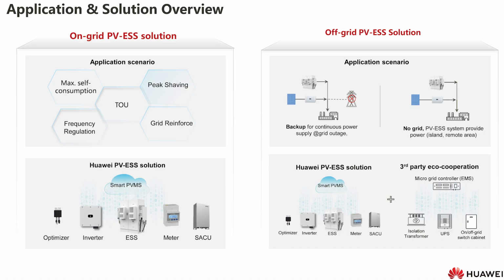You'll get clinics, and the guys are punting for clinics and schools and so on to be in a situation where they won't be load shedded. The problem there is that they're all sharing the same substations, so they would have to have many separate subs so that they don't have to switch them off. But that is why we're talking about on-grid. For on-grid, you can do maximum self-consumption, frequency regulation, time of use, peak shaving, and grid reinforcement as well. For that, you could use the following items: an optimizer, inverter, ESS, meter, and SACU.